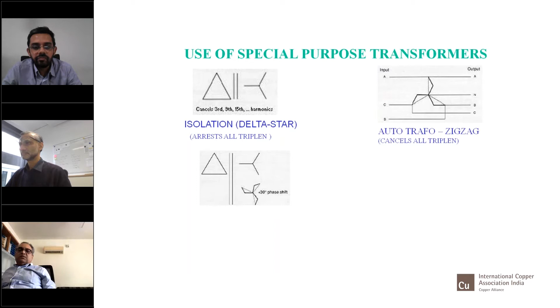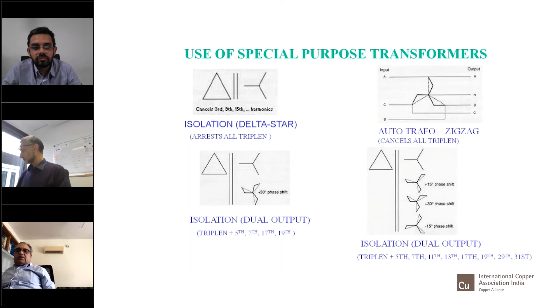Use of special purpose transformers that I was talking about, delta star, which are used in PDUs. Then you have these auto transformers, zigzag. You have isolation, dual output. You have quad output. Various kinds of equipment are there. These are all generic things that I'm putting here. Where anybody has a problem, they will have to consult a specialist, and he would give a solution exactly suited to your requirement if you face a harmonic issue. Then there are filtering and absorptions.